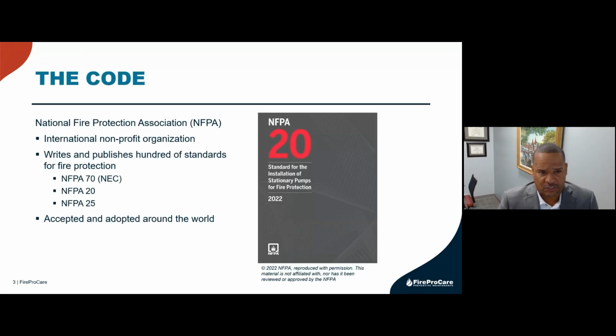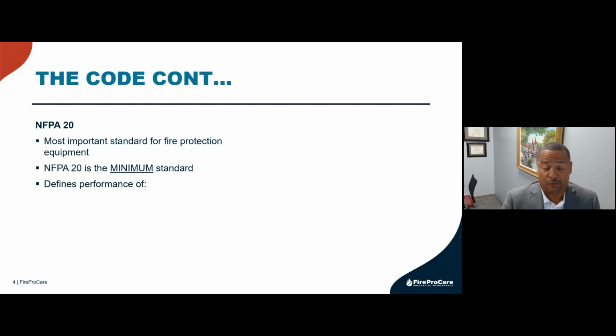The National Fire Protection Association is a global organization that actually writes hundreds of standards. The three you see on the screen now: NFPA 70, which is the National Electrical Code, NFPA 20, which you see the picture of that publication on the screen, and NFPA 25. These are probably the three most important to the fire pump industry because they detail and guide us on how we design our products. Now, the other thing to remember is whenever you hear someone talk about a listed product, what they're talking about in fire protection is, at least in the US, a third party organization that has come in and basically approved or listed your equipment as meeting a standard. The standard for fire pump controllers is NFPA 20, and that is what we use. We call it our Bible to get things done.